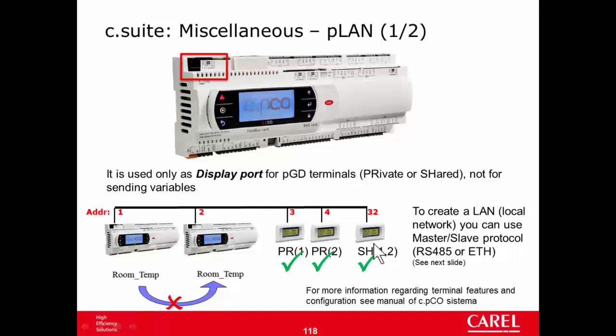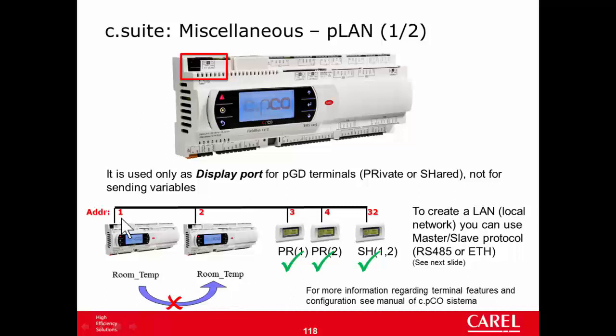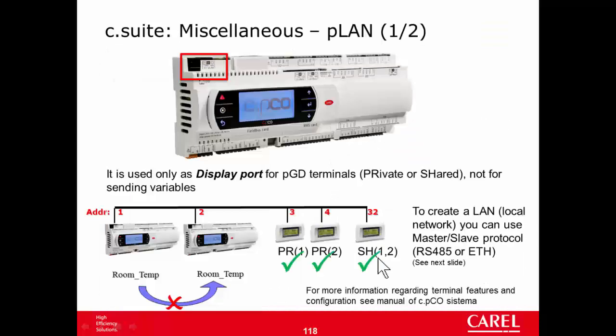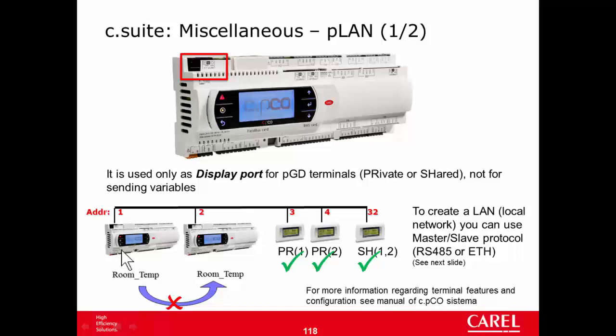In this example, this terminal is configured as private of terminal one, so here I will see only the mask of this device, this c.pCO. This is configured private of two, so here I will see the mask only of this one. And this one is configured as shared by the two. So using a system menu or some system function in CMask, it is possible to show the mask of unit one or number two.